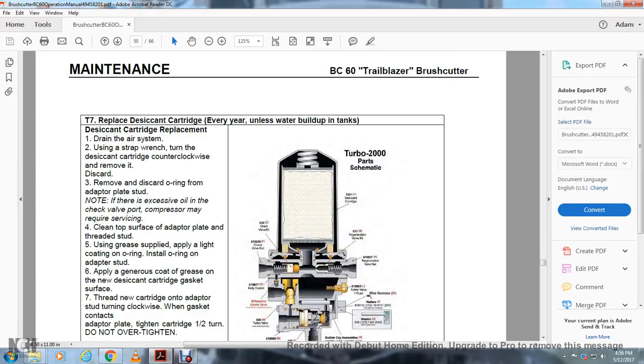Alright, T7, the replacement of the desiccant cartridge every year, unless water builds up in the tanks. For the desiccant cartridge replacement, drain the air system, use a strap wrench to turn the desiccant cartridge counterclockwise, then remove and discard it. Remove and discard the O-ring from the adapter plate stud. Note that if excessive oil is in the check valve port, the compressor may require servicing. Clean the top surface of the adapter plate with the threaded stud. Use the grease supplied to apply a light coating to the O-ring.